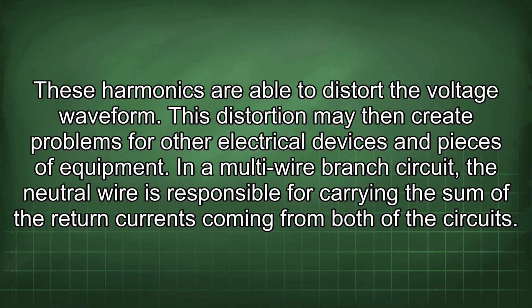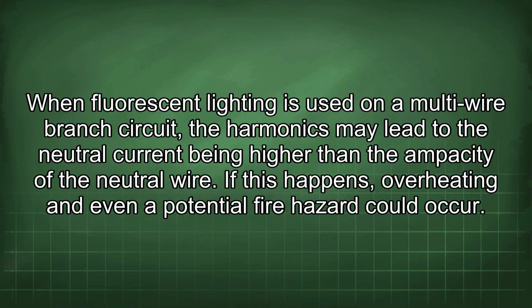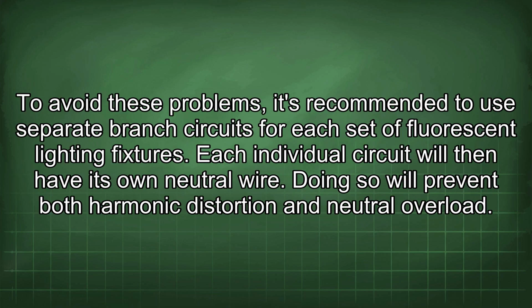In a multi-wire branch circuit, the neutral wire is responsible for carrying the sum of the return currents coming from both of the circuits. When fluorescent lighting is used on a multi-wire branch circuit, the harmonics may lead to the neutral current being higher than the ampacity of the neutral wire. If this happens, overheating and even a potential fire hazard could occur. To avoid these problems, it's recommended to use separate branch circuits for each set of fluorescent lighting fixtures. Each individual circuit will then have its own neutral wire. Doing so will prevent both harmonic distortion and neutral overload.